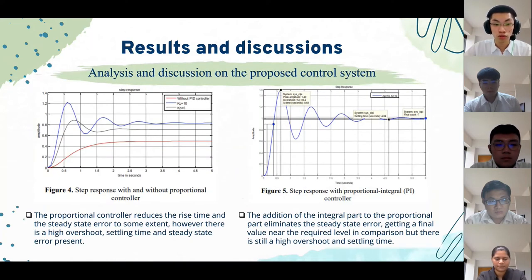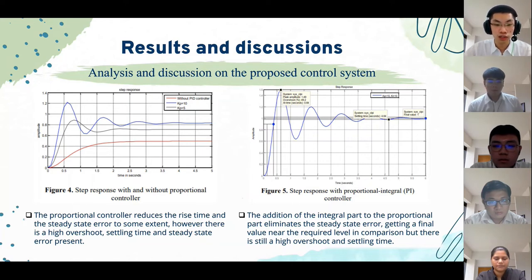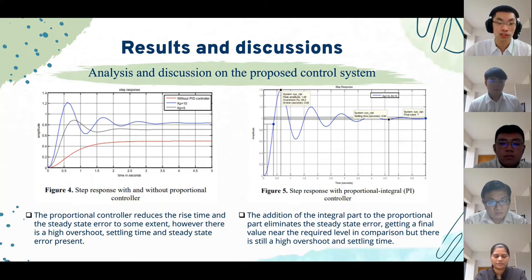In order to control water level, a variety of process control strategies are applied. The use of a proportional (P) controller reduces rise time and steady-state error compared to no controller. However, there is high overshoot, settling time, and steady-state error present. The addition of the integral part to form a PI controller eliminates the steady-state error and achieves a final value closer to the required level compared to the P controller, but there is still high overshoot and settling time.